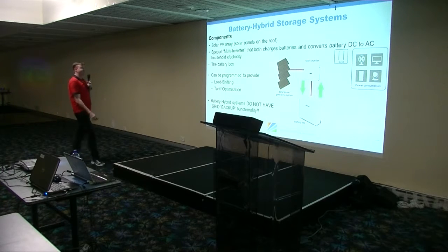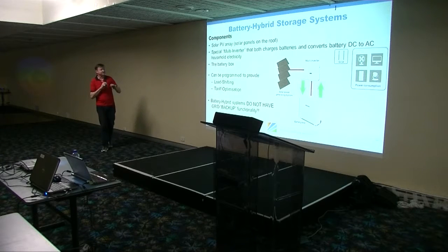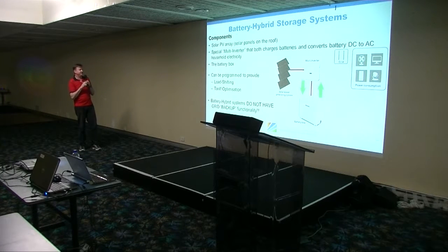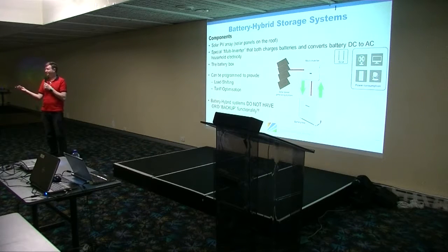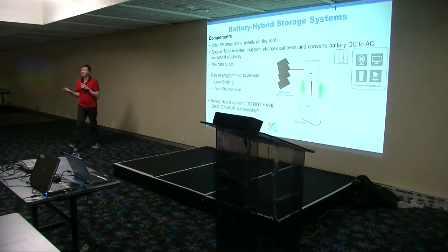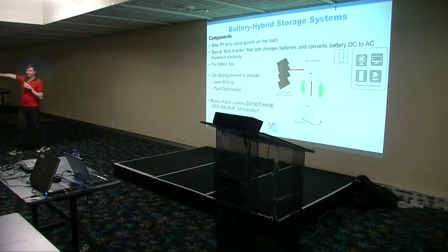So the other one is the battery hybrid system. And this one's different. Whereas the UPS will maintain power to select loads, with this system the power shuts off on all loads. We all know, we all have solar, 85% of this room has a solar system on their roof already. So what happens when the power shuts off on your solar system? What happens to your inverter? It shuts down. Does anyone know why that happens?